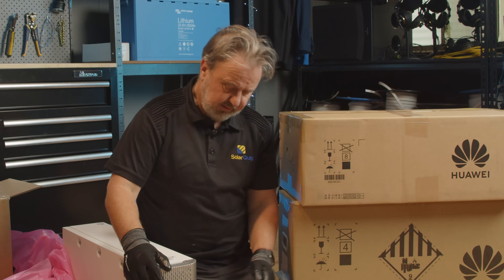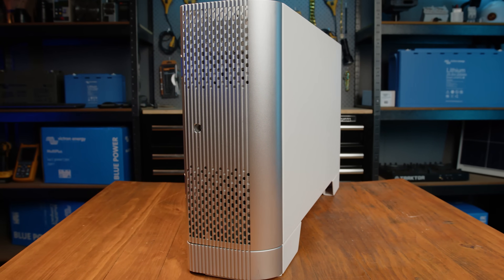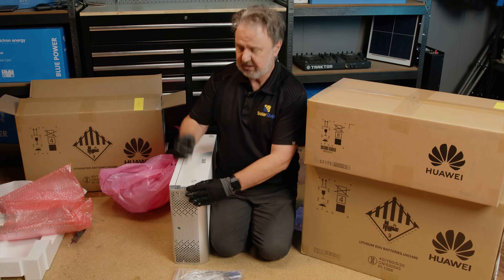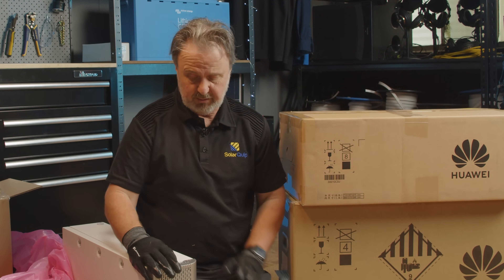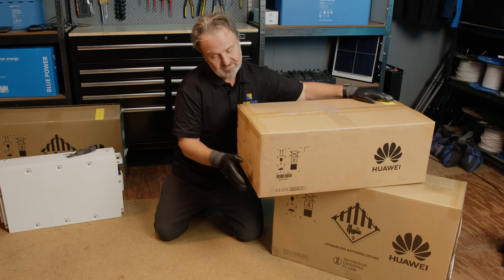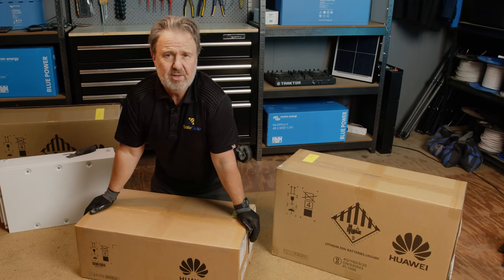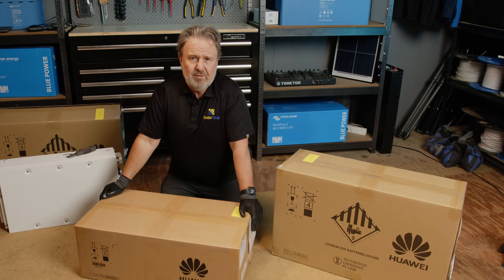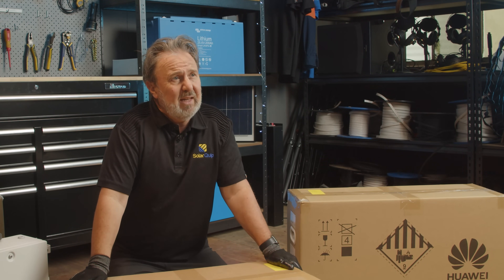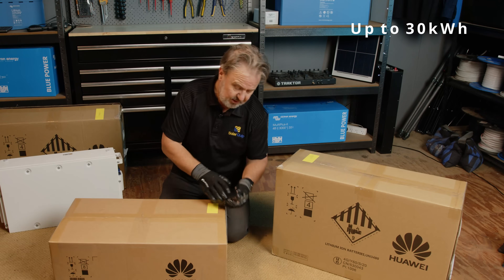These covers cover the cables and provide a pleasant aesthetic to the side of the unit. The next battery module goes on top, and the cables from the unboxing connect the next battery module in parallel — that's how the modules work. The controller sits on top; it does the role of the battery management system managing the parallel battery modules, but it's also a DC-DC converter so it can match the voltage the hybrid inverter requires. These batteries are designed to work with Huawei's hybrid inverters and they come in single phase and three phase in a range of sizes, so you can build pretty big systems with these small modular batteries.